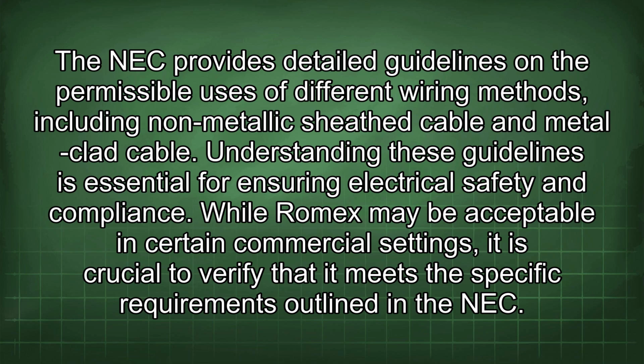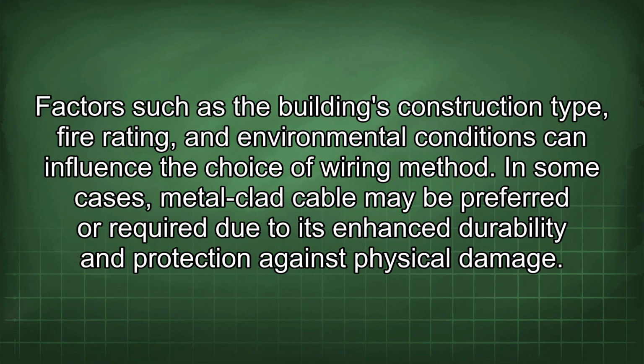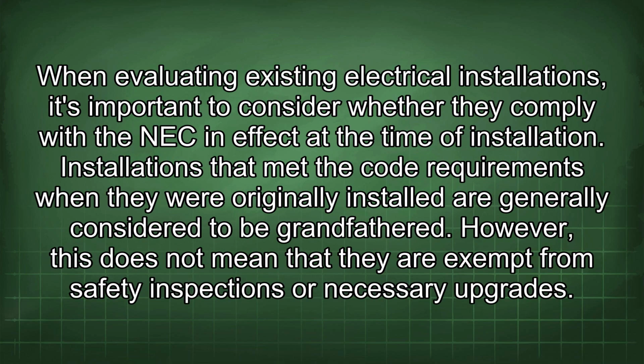While Romex may be acceptable in certain commercial settings, it is crucial to verify that it meets the specific requirements outlined in the NEC. Factors such as the building's construction type, fire rating, and environmental conditions can influence the choice of wiring method. In some cases, metal-clad cable may be preferred or required due to its enhanced durability and protection against physical damage. When evaluating existing electrical installations, it's important to consider whether they comply with the NEC in effect at the time of installation.